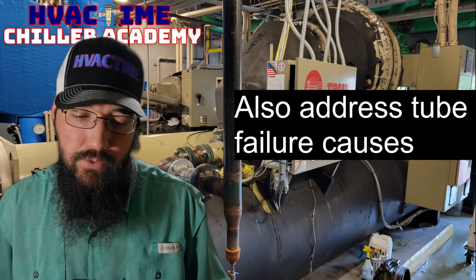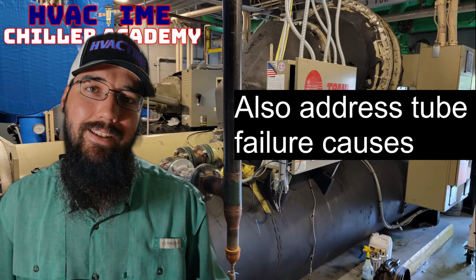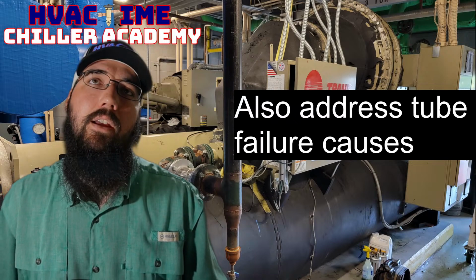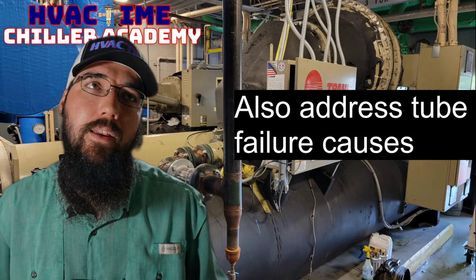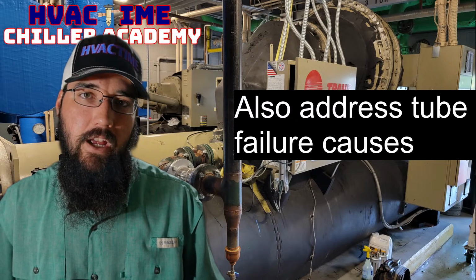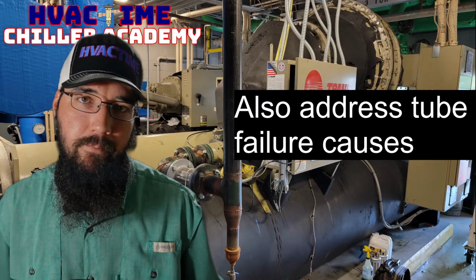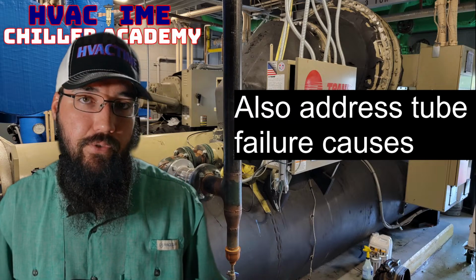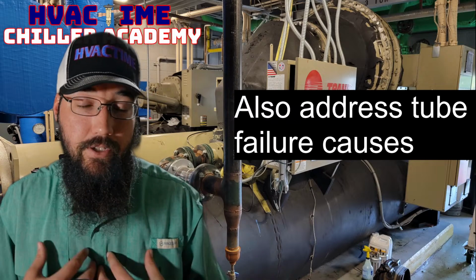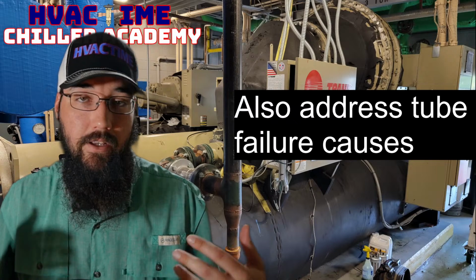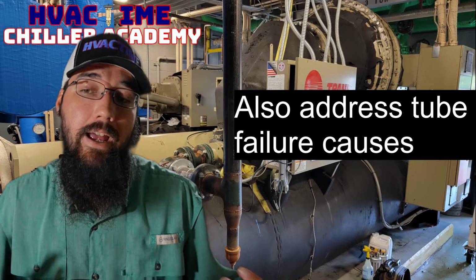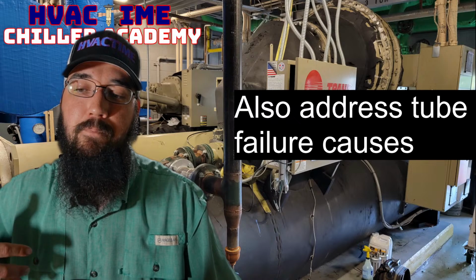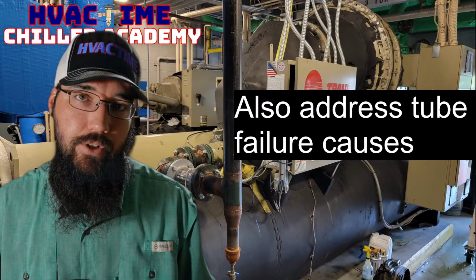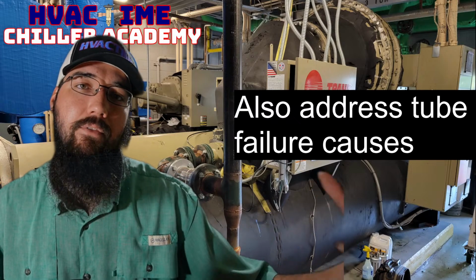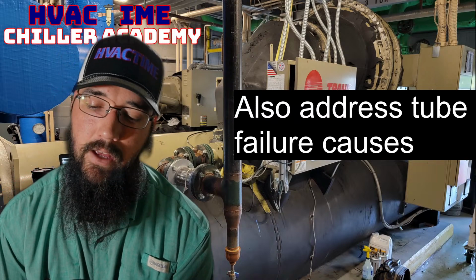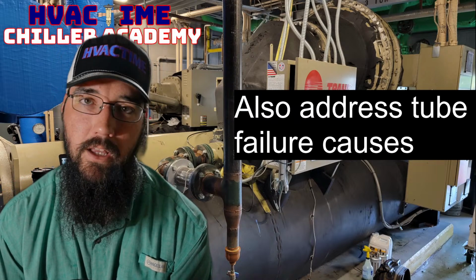One of the saddest ways of having a tube failure is to have the tube freeze. Now, there are two cases where this could happen. One, you could have a genuine freeze at your facility. We actually had this happen in Texas, and it devastated us because we don't have the same winter protection, like winterization, that you have in other places, such as we don't run glycol in our loops.